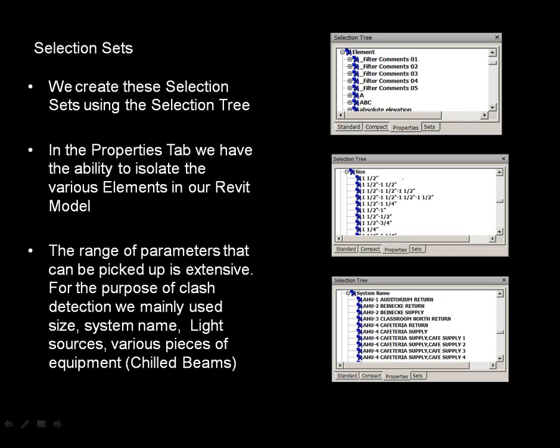It became very important to us later on. We realized that not only did we need the ability to go into Navisworks and get it to look inside Revit for parameters like sizes and equipment, but we needed more than that. We couldn't have every 1-inch pipe in the entire model on one set. We needed to break it down further, to have every 1-inch chilled water pipe isolated, every 2-inch hot water pipe isolated, because each of these required different insulation and different rules. We'll come to that in tolerances, but that demonstrates the starting point.